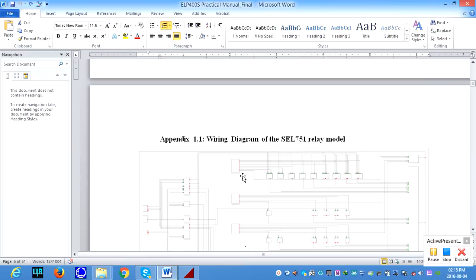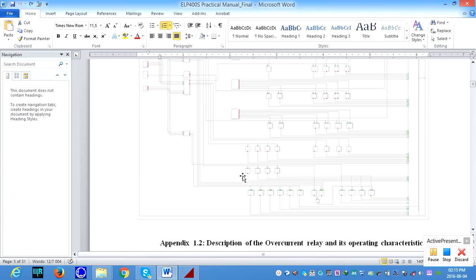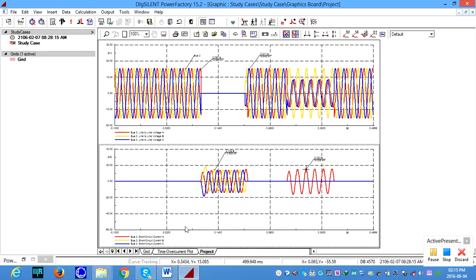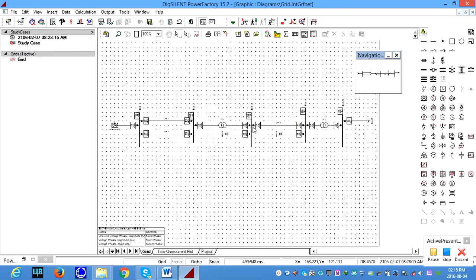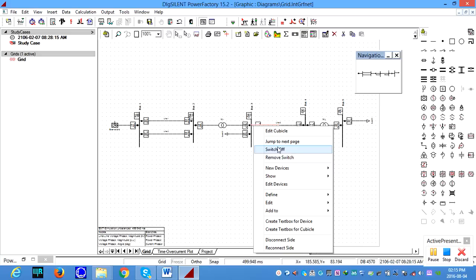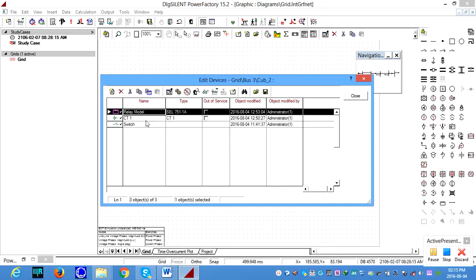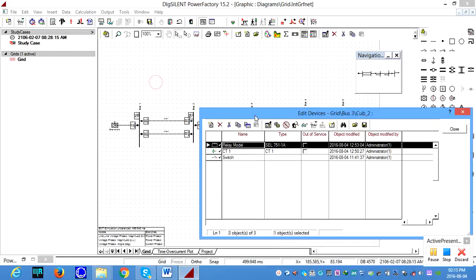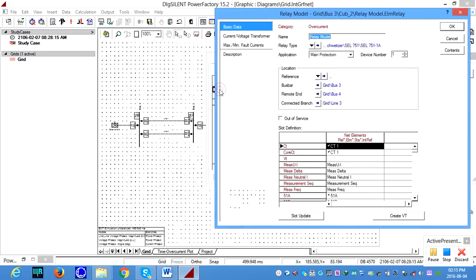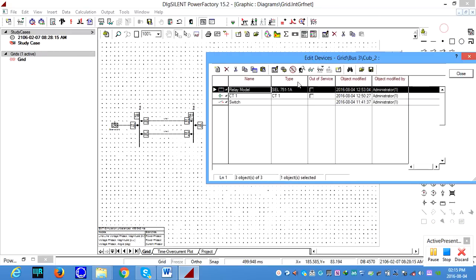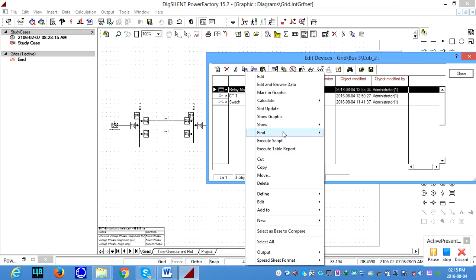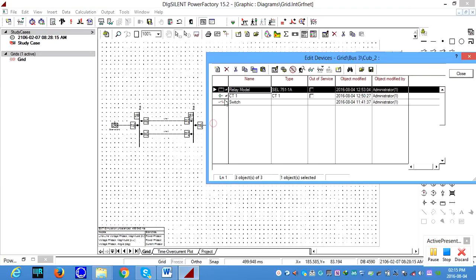The last one, we also want to look at the relay wiring diagram, which is shown in appendix 1.1. In order to do that, you can go to this model here and edit the devices. If you edit devices, you can see what elements are available in that cubicle. You have a relay model. Right click the relay model, and then you can show. Either you can add a time overcurrent plot or existing protection, but we are looking at show graphics. So make sure on the left side you right click and go to show graphic.